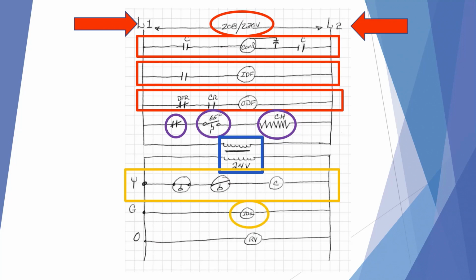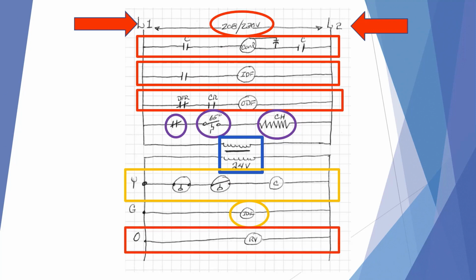Here we have the indoor fan relay on our blower or G circuit, that when this is energized, the indoor fan motor will run. We also have here the reversing valve circuit, which is our O circuit, that when this line is energized, the reversing valve will switch and either put us in cooling or heating depending on what the energized cycle does.